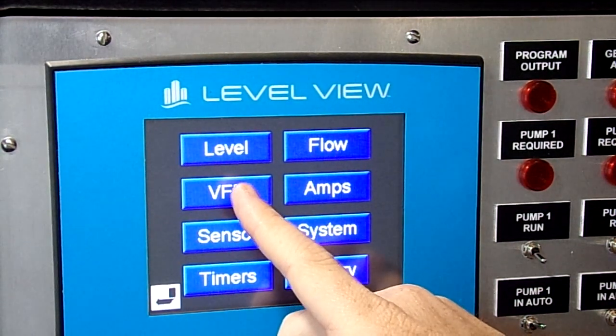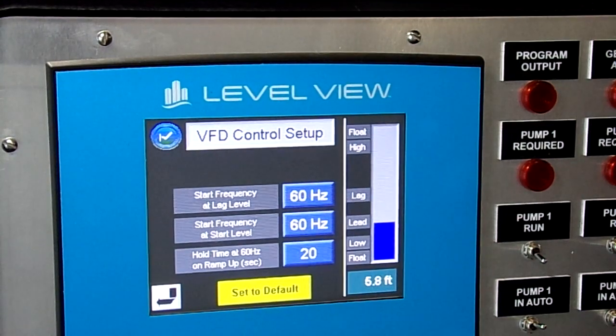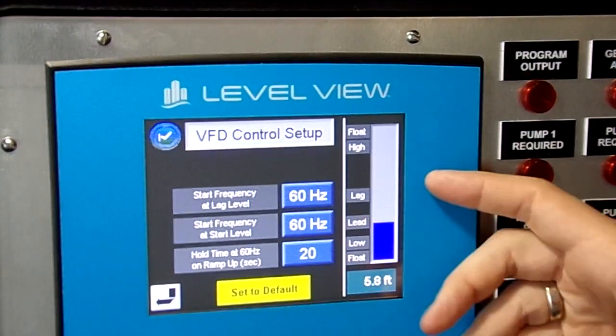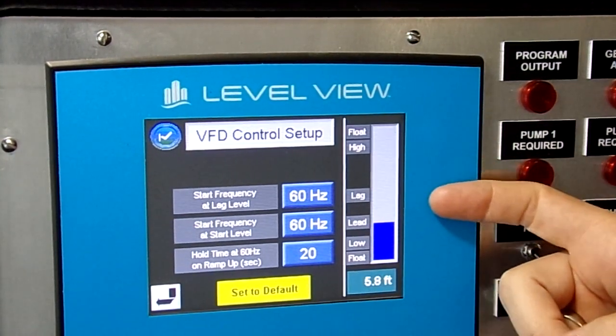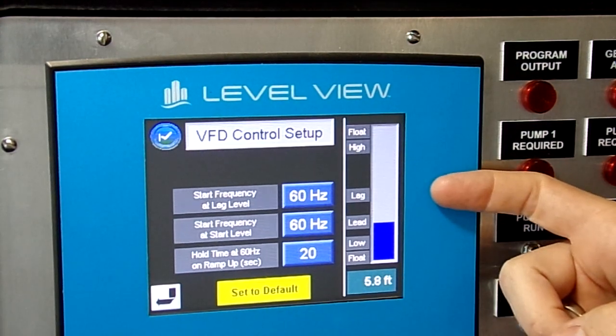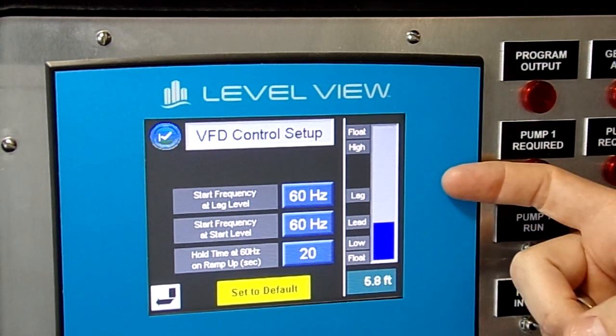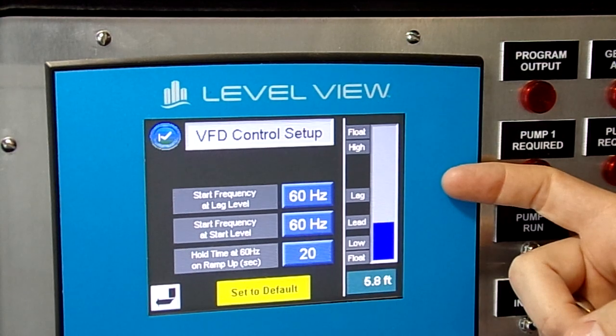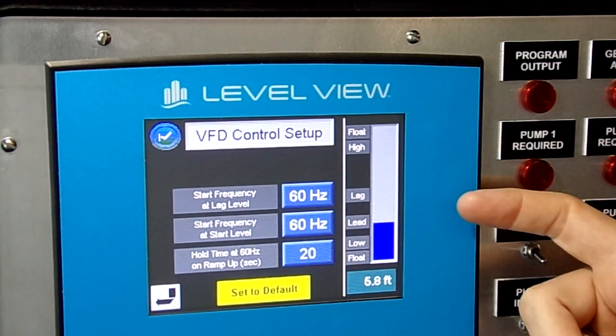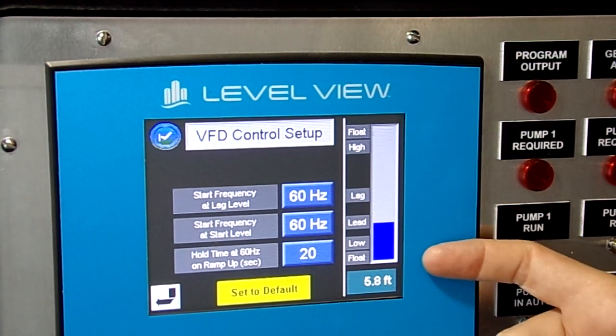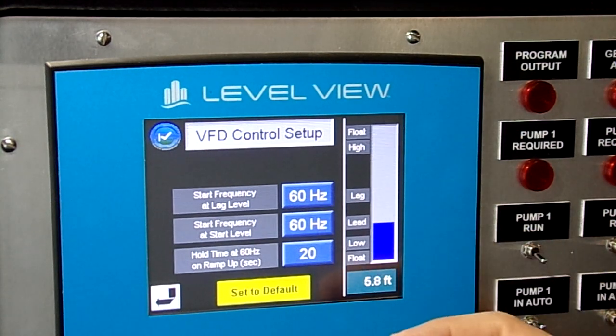If we go to our VFD, it will come enabled, and for most grinder stations you'll want to have these set for 60 Hertz on start and lag. The lag can be slowed down if you want to run for more energy efficiency later on different pumps. It also has a hold time at 60 Hertz for how long it needs to hold at 60 Hertz.